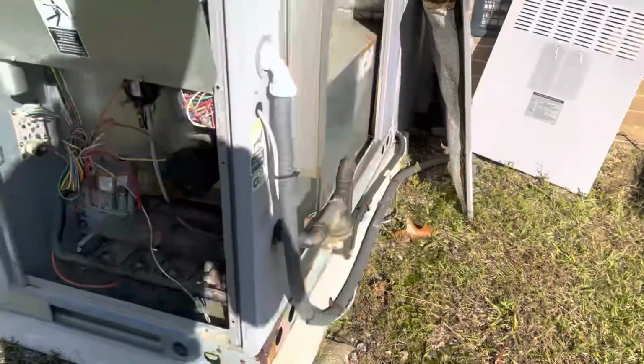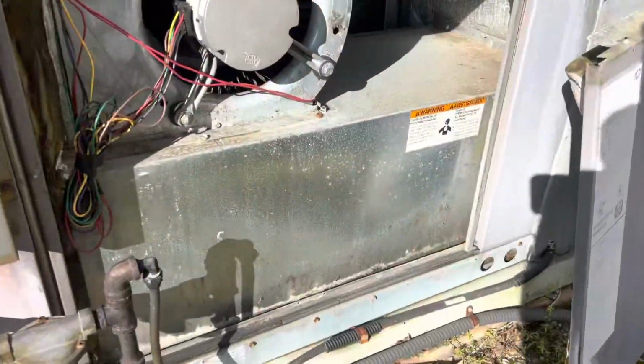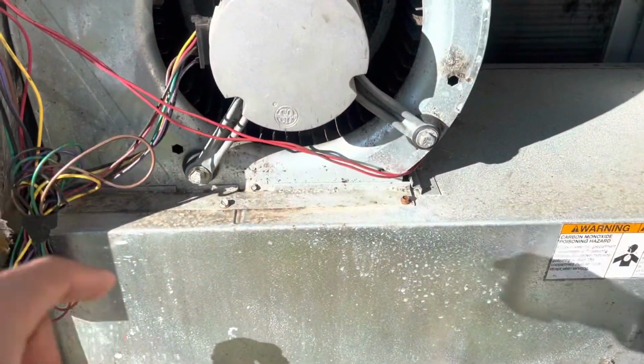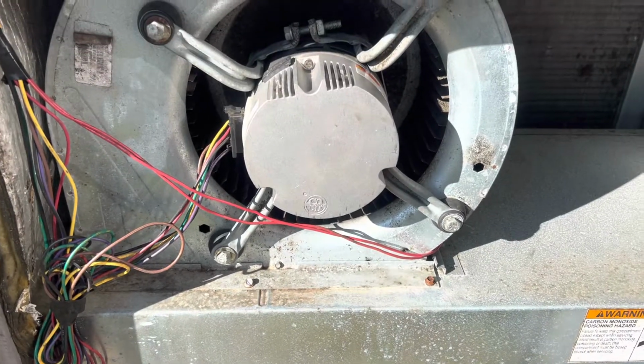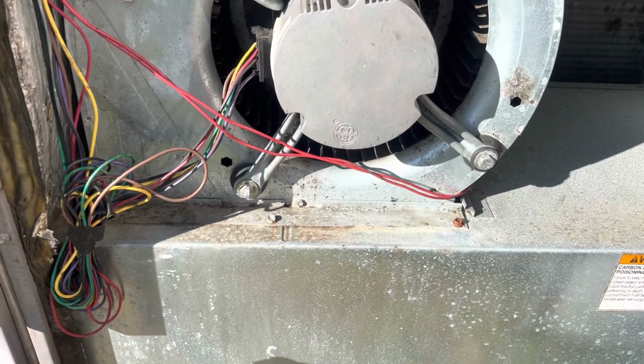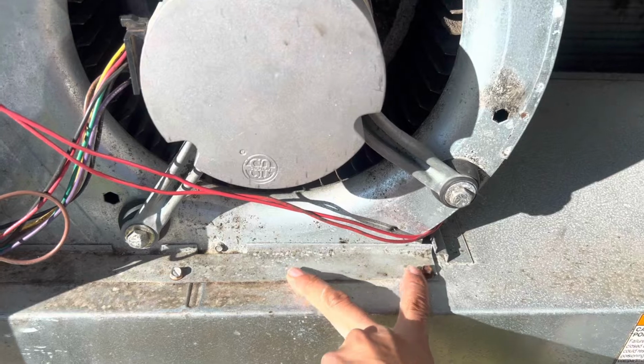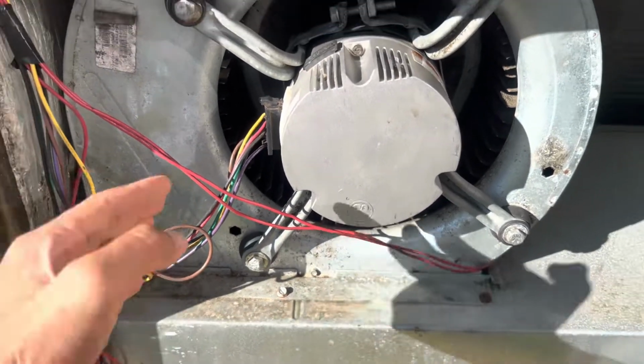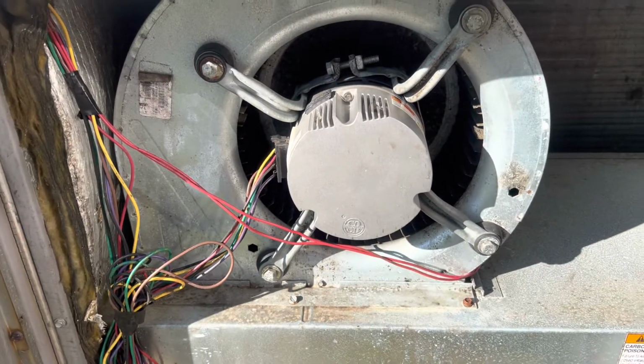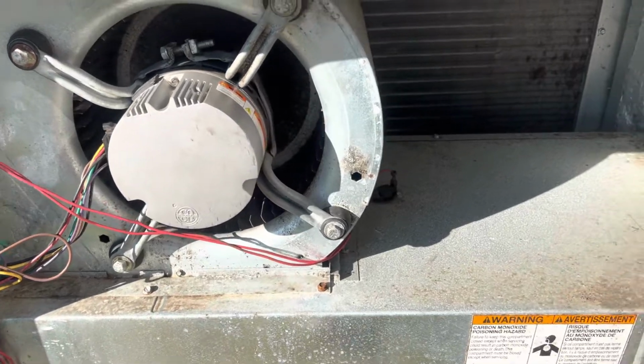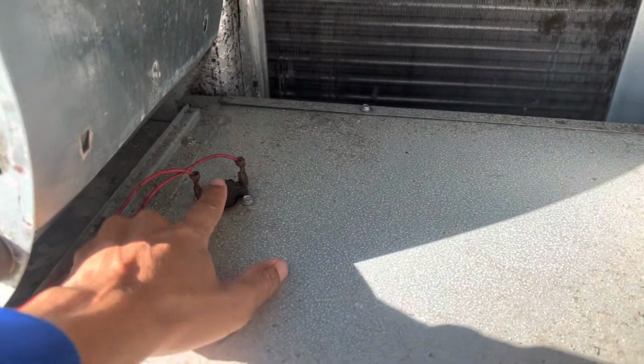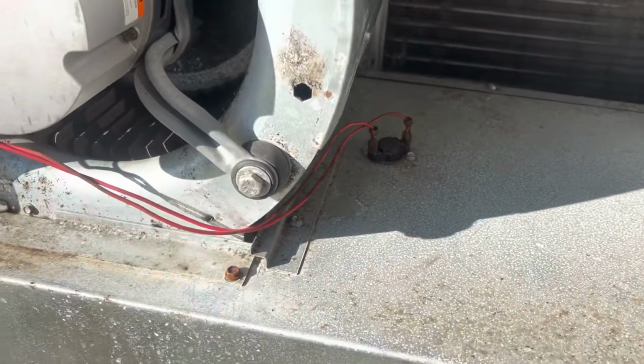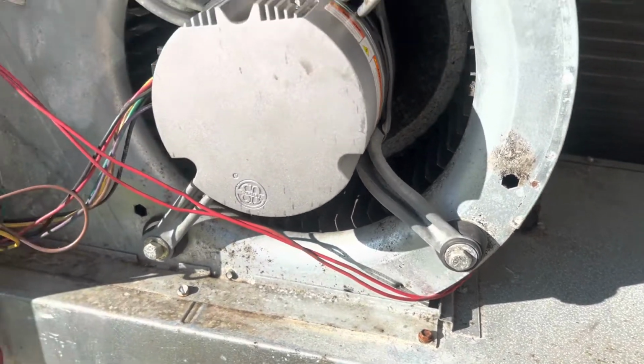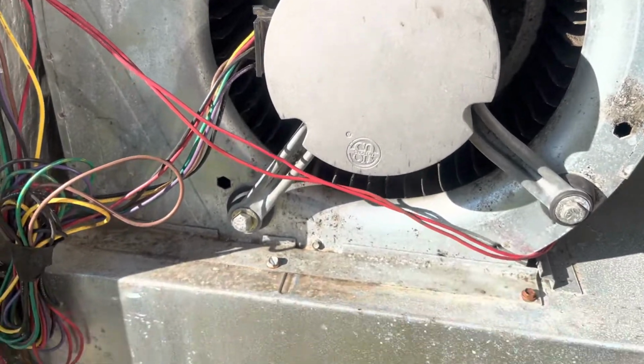All right, let's take a look over here. The heat exchanger is under here. I'm going to show you how that looks and show you how to inspect that. So what we're going to have to do is take these screws off. We're going to have to slide this motor out and take a look at that heat exchanger under there. If you notice, there's also a safety here. That's going to be your high limit, okay? All right, let's check it out.